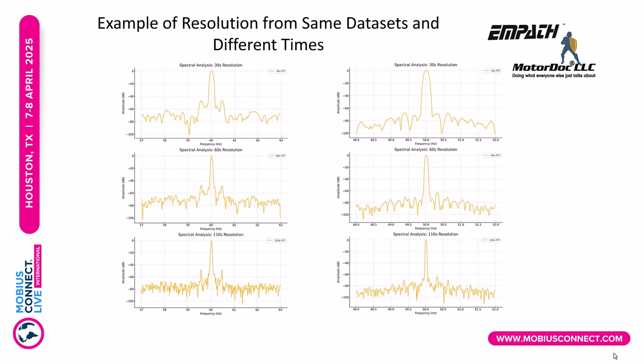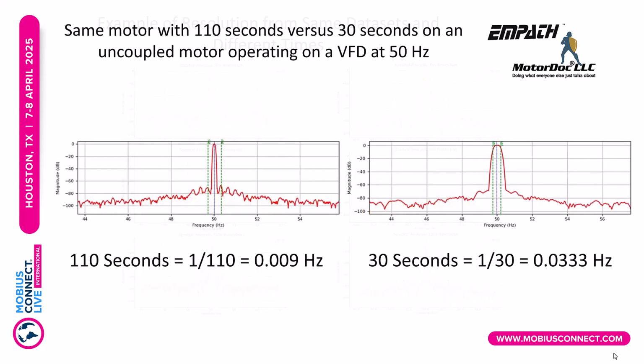This becomes important when we start looking for machines sitting on, say, the shop floor. Here's a good example of that. So if I'm looking at an unloaded machine, and this is an unloaded machine running at 50 hertz, on the left at 110 seconds, you can see that the bin size is good enough that I can look at pole pass frequency peaks at 0 load. That means that I am looking at the condition of the rotor at 0 load, uncoupled with full voltage on a power supply. On the right-hand side, this is where I just take a 30-second snapshot. It's now blended in with my primary peak, meaning that I cannot distinguish those pole pass frequencies, so I'm not aware that there's casting voids present in that rotor. This becomes more serious if I actually have broken rotor bars in those conditions.